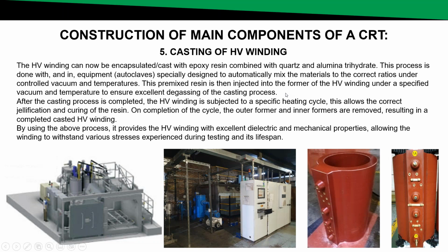Should we not degas the casting process properly, you will commonly find porous areas in your casting, and this would lead to high PD levels of the HV winding, which will eventually result in failure of the transformer. So it's very important that this whole entire casting process is done under very strict, controlled and automated conditions. So once the casting process has been completed, the HV winding now needs to be subjected to a heating cycle.